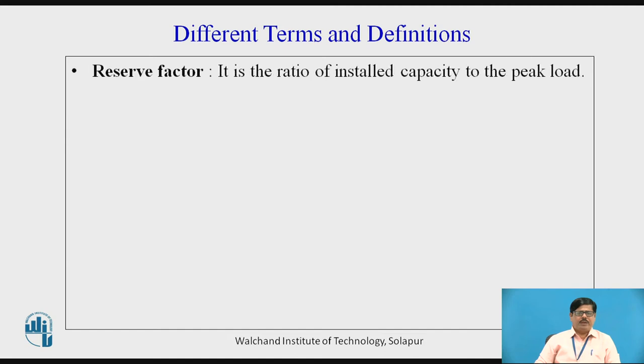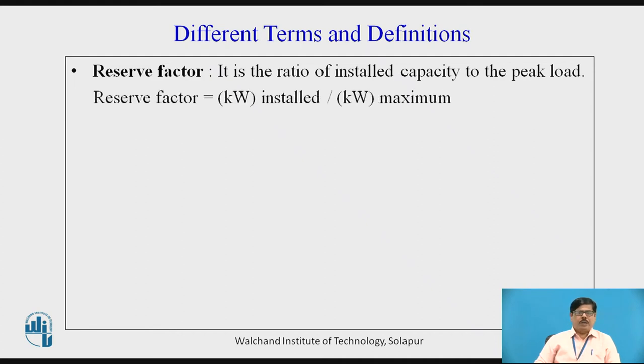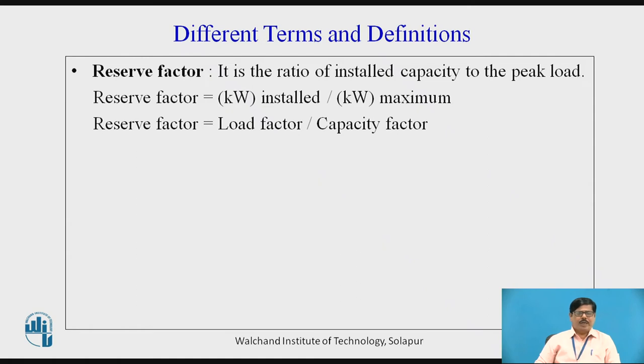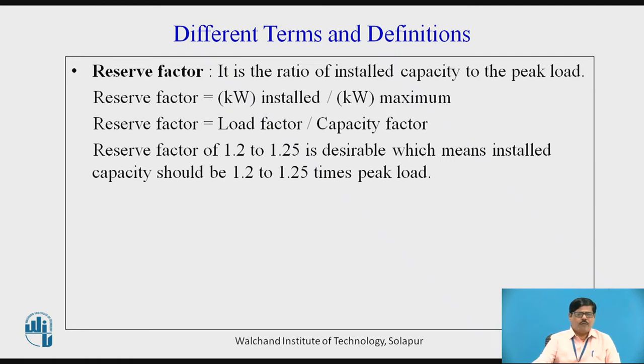The reserve factor is the ratio of installed capacity to the peak load. It can be expressed as kilowatts installed divided by kilowatts maximum utilized. If we divide the load factor by the capacity factor, we get the same expression — kilowatts installed divided by kilowatts maximum. Therefore, the reserve factor can also be expressed as the ratio of load factor to capacity factor. A reserve factor of 1.2 to 1.25 is desirable, meaning installed capacity should be 1.2 to 1.25 times the peak load so that the plant will not be overloaded.